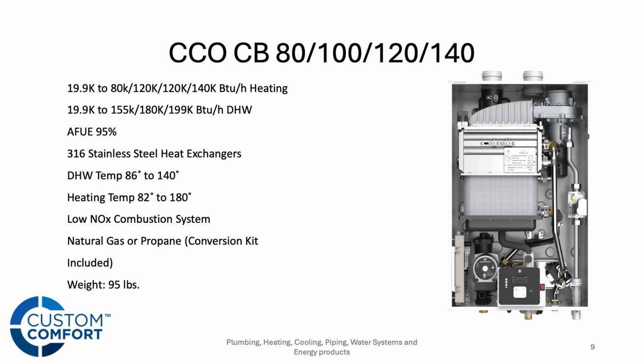Starting with the combi, we've got 4 different sizes on the combi, and we have a 95% AFUE 316 stainless steel heat exchanger. These are gonna have domestic hot water temperatures with capabilities going up to 140 degrees. On the heating side, we're gonna go up to 180 degrees. All of the boilers that we're gonna talk about tonight are going to be natural gas out of the box, but they all come with an LP conversion kit in the box as well.